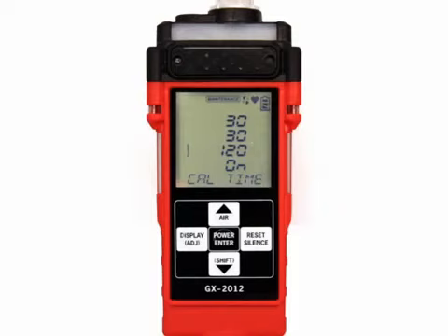To update the AutoCal setting, use the Shift button to scroll to the AutoCal value. The factory setting is on. With AutoCal set to on, if a bump test fails, the unit will automatically begin a calibration. If AutoCal is set to off and a bump test fails, nothing will happen.